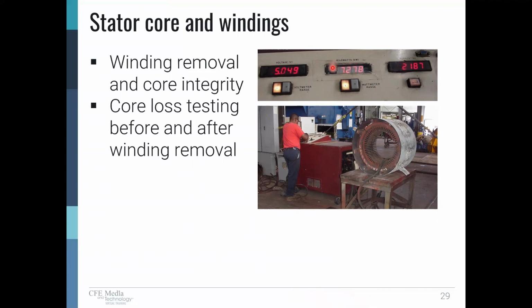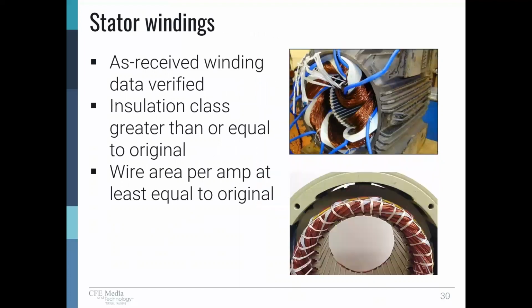And then this is the kilowatt, 7.2 something. So we've got over 7,000 watts of energy magnetizing the core, and we're testing for heating of the core. And also we measure that watts loss. And we can compare. The windings have been removed from this one. So this, let's call it 7.3. We'd compare that to the original incoming when the windings were still in it. And if it was 7.3 before and 7.3 after, we now have validated that we haven't changed the core losses.